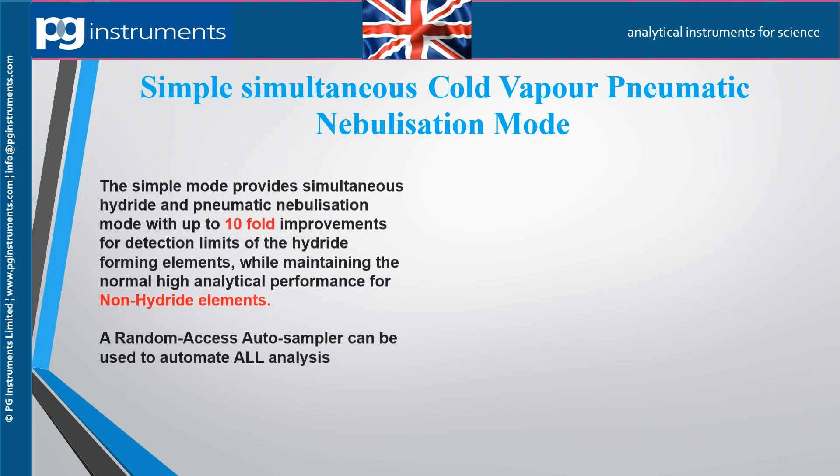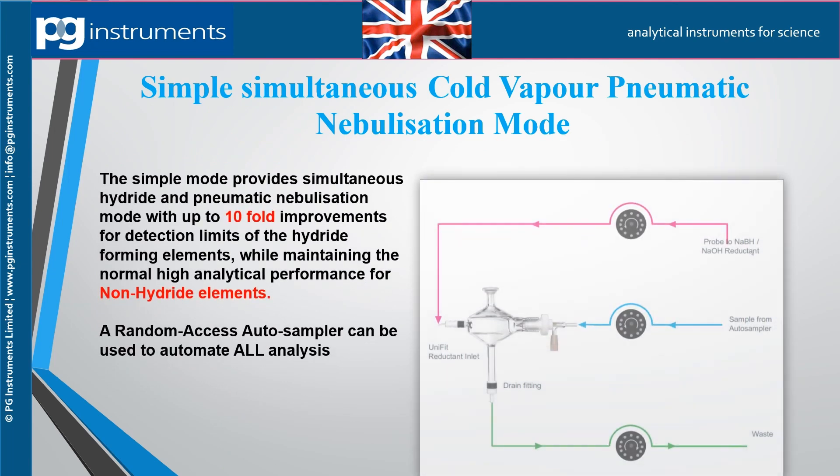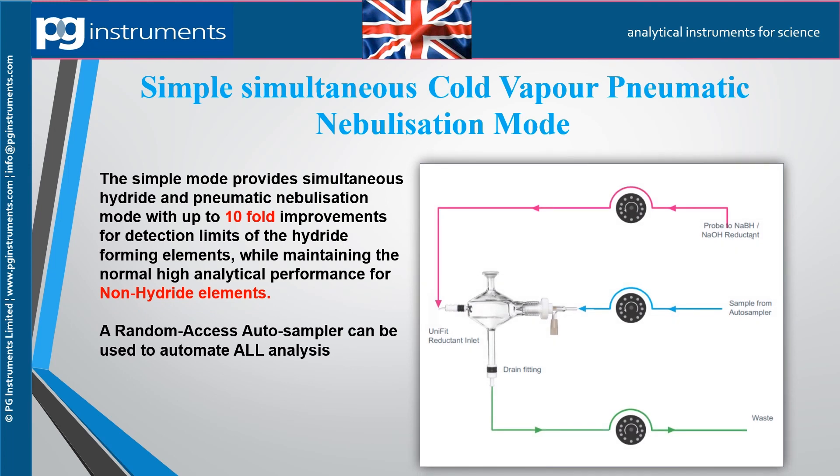The simple mode provides simultaneous hydride and pneumatic nebulization with up to 10 fold improvements in detection limits for hydride forming elements. This method requires three peristaltic pump channels: one for the reductant, a second for the sample, and a third for the drain.